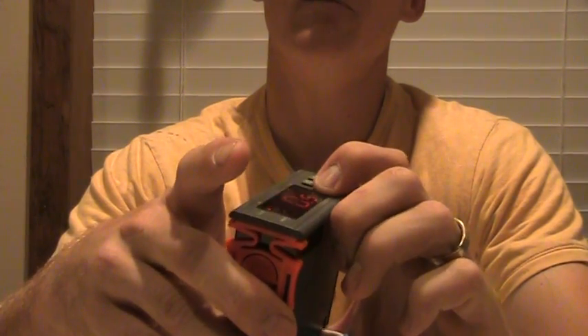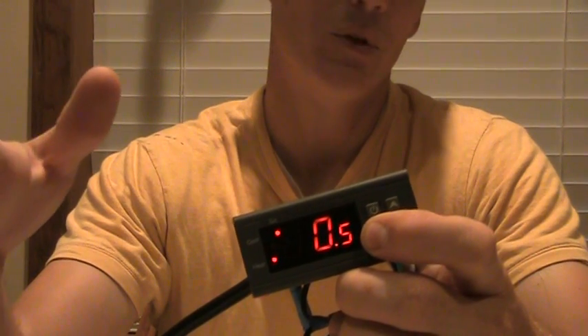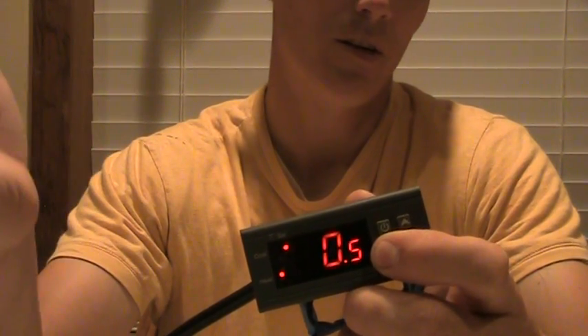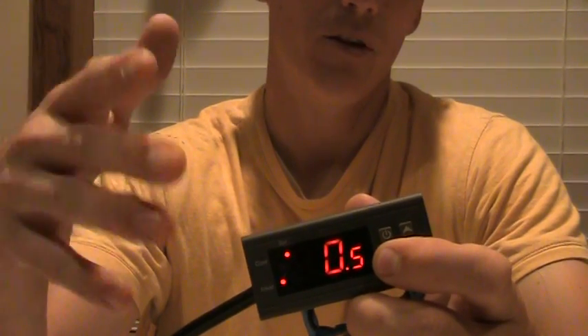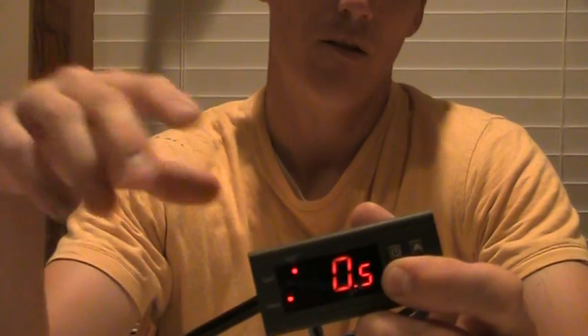Hold your S key, and you'll see it says 0.5. That's the variance. It'll cut on if it falls within half a degree. If it falls half a degree low, it'll cut on the heat. If it goes half a degree high, it'll cut on the cooling side.